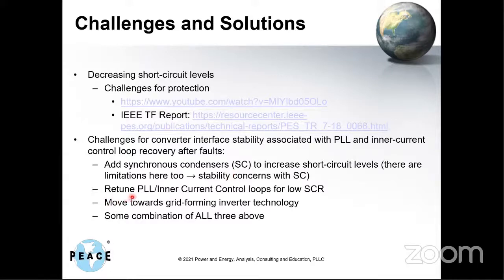Another option is to retune the PLL and inner current control loop for the weaker conditions, or move towards grid forming inverters, or all of the above. You may need a combination of all these things: some grid forming, some retuning of the PLL, a couple of synchronous condensers placed strategically in the system. And one of the other things, I skipped that, let's go back up here.